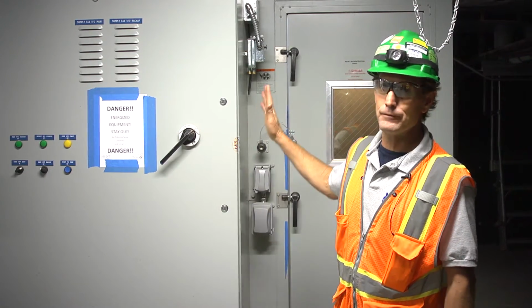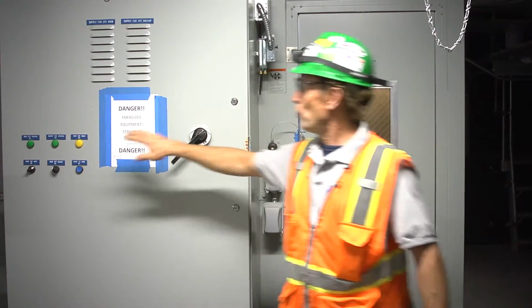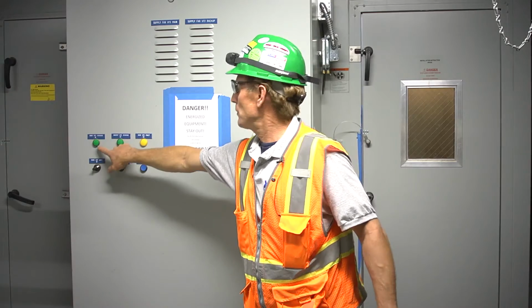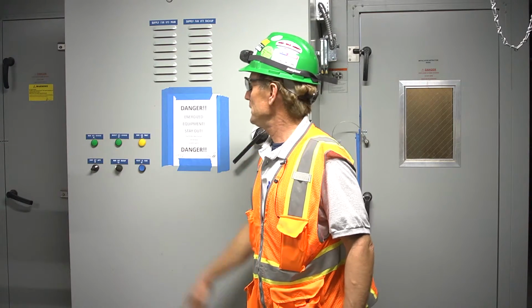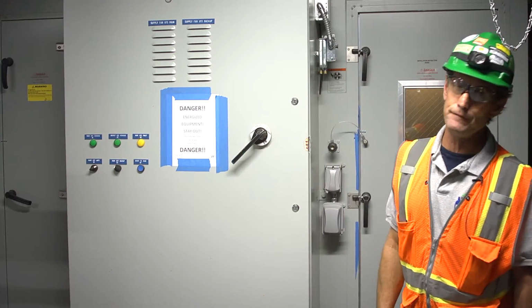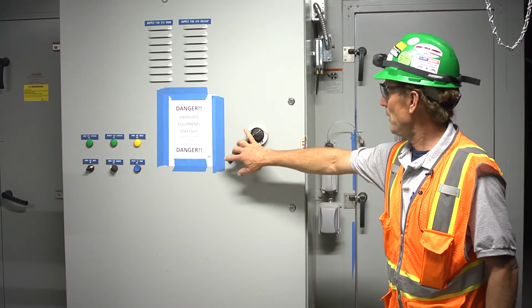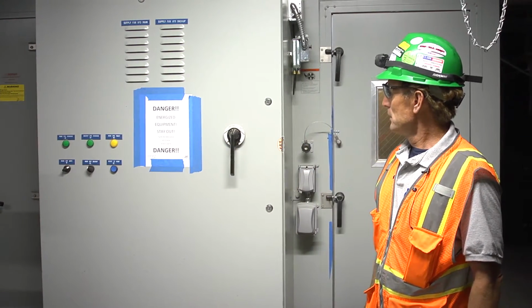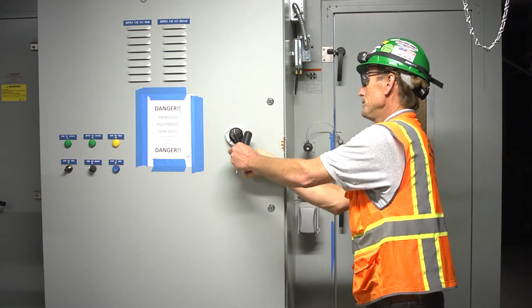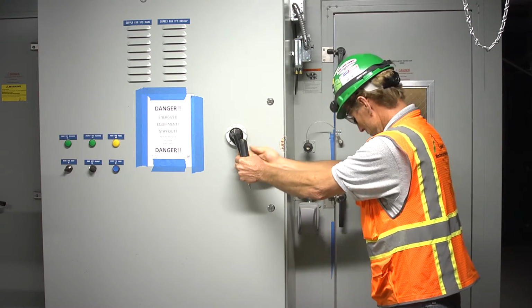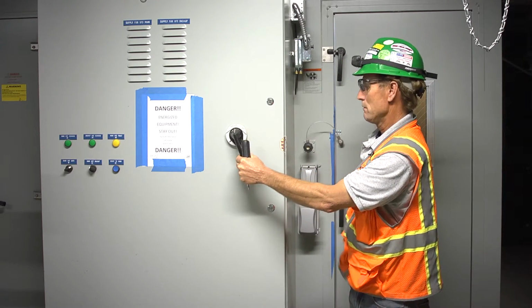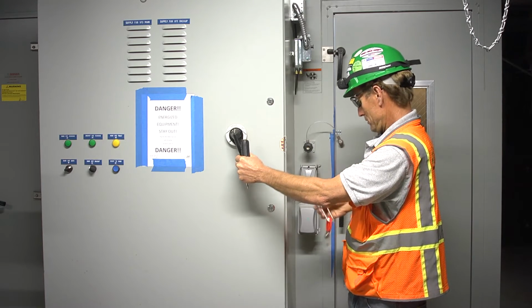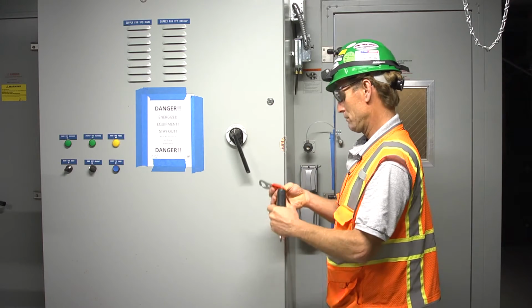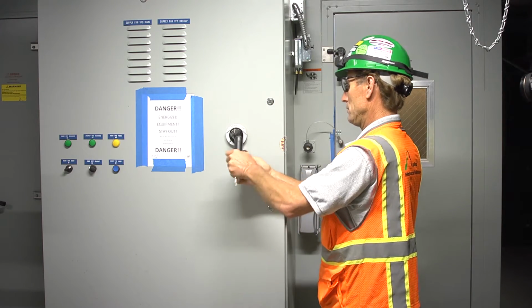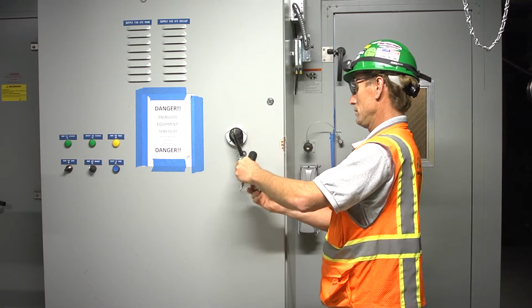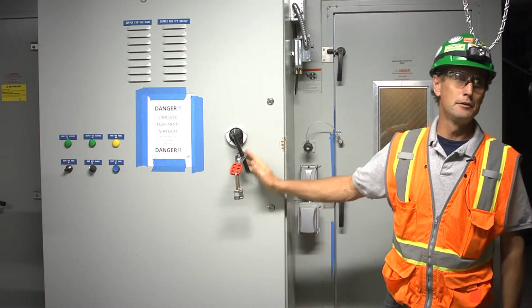So for the purposes of instruction, we're going to go ahead and secure the power. Normally, when the unit is running in normal operation, this green light will be lit, indicating the main supply fans are running. So we're going to go ahead and secure power here. And there's a Lockout Safety hasp on the back of this that we could then lock out here, and the unit's now safe to enter.